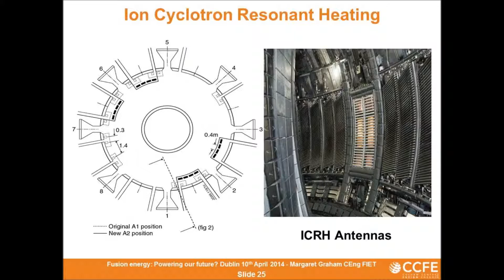We used to have a different type of 2-strap antenna, which gave us 22 megawatts of coupled power into plasma. And with this particular scenario, we've had 60 megawatts of power. We've also now installed, which is this one, what is called the ITER-like antenna, which has a matching system of capacitors actually inside the vacuum chamber itself. So we've got 5 antennas in there. We have 16 2-megawatt RF generators, frequency as we've explained, and they've got the HVD supplies that you saw coming from the 400 kV feed, so we've got 37 kV feeds on there. We've got 4 4-strap antennas, as you just saw in the previous slide, with getter pumping, so they've got vacuum scenarios that we have to look after to make sure we keep the vacuum.